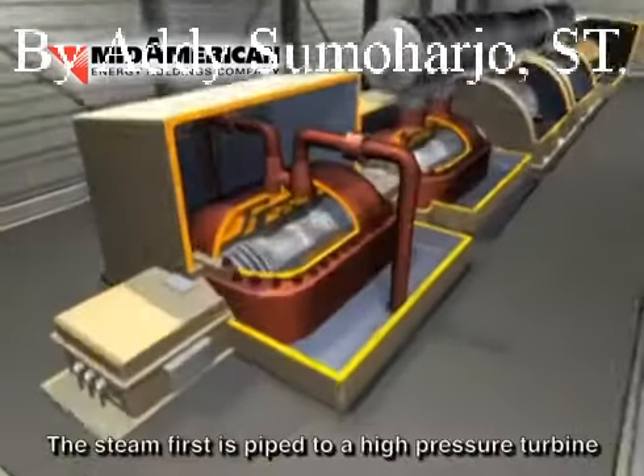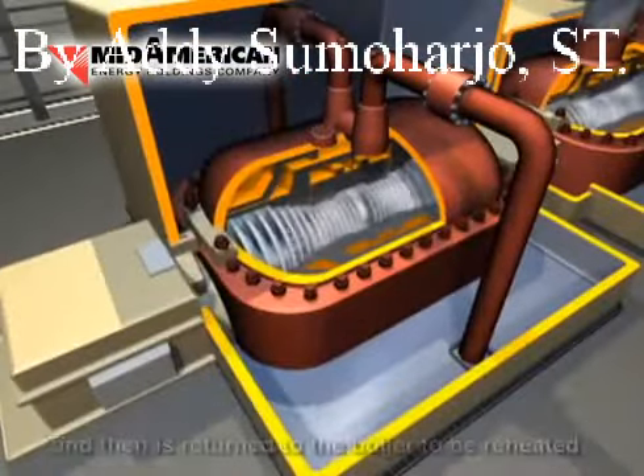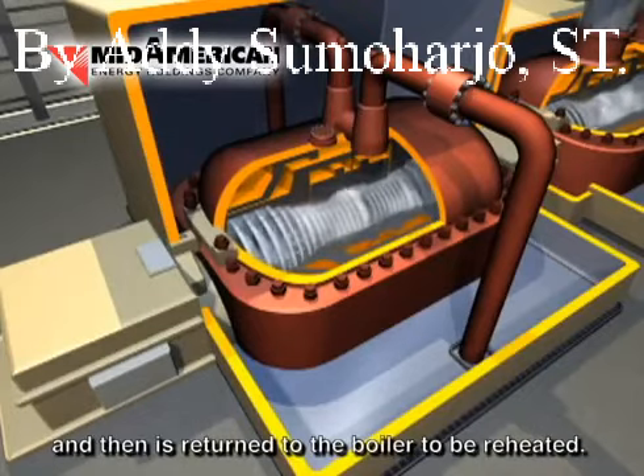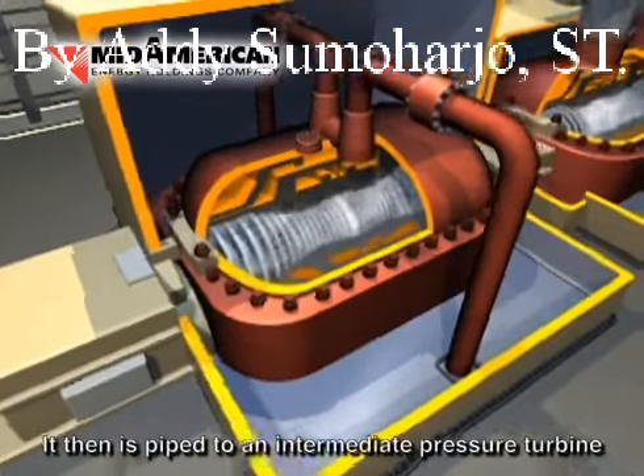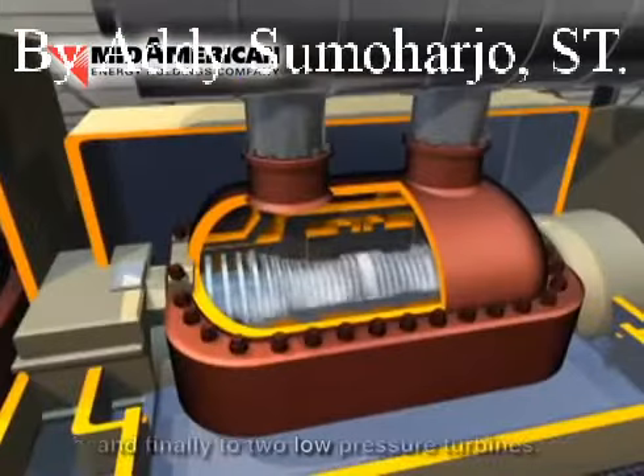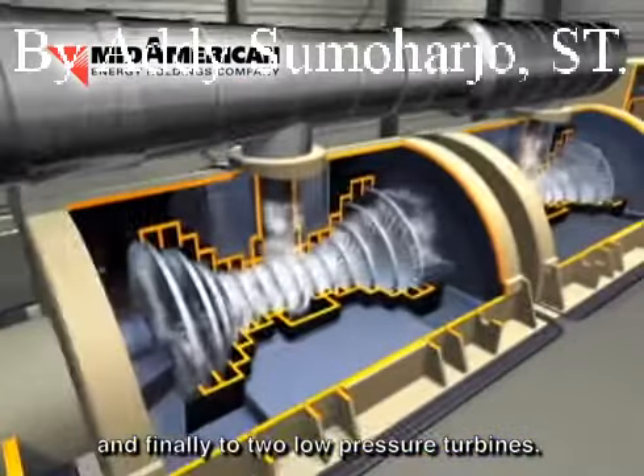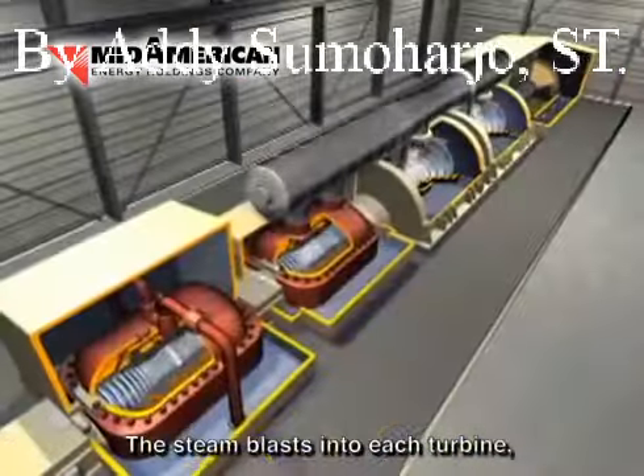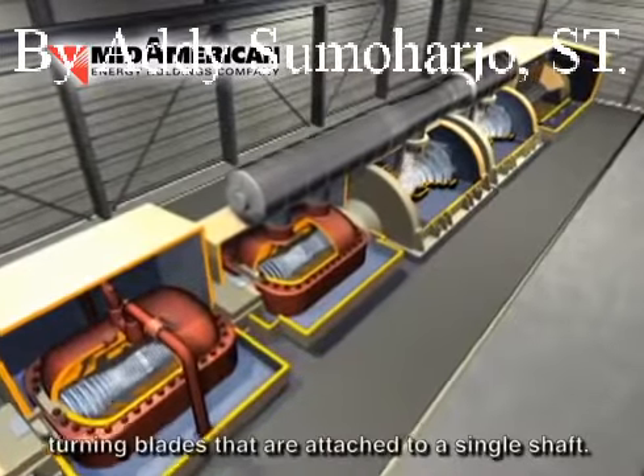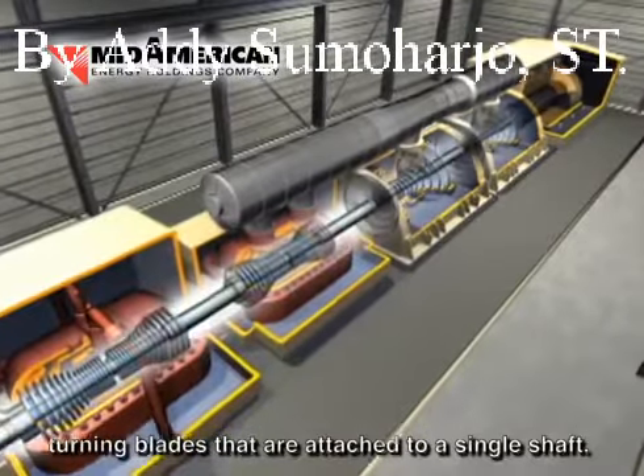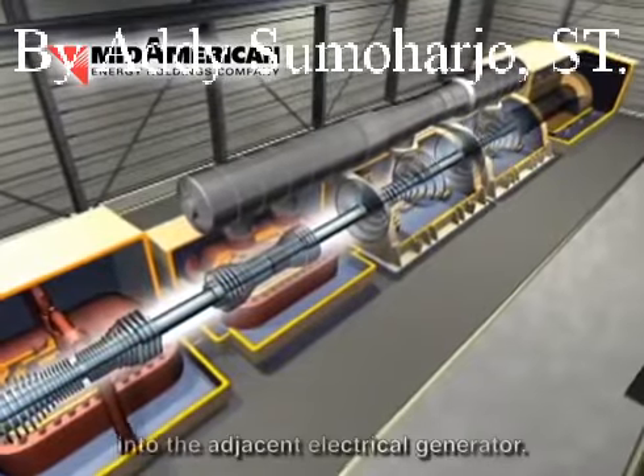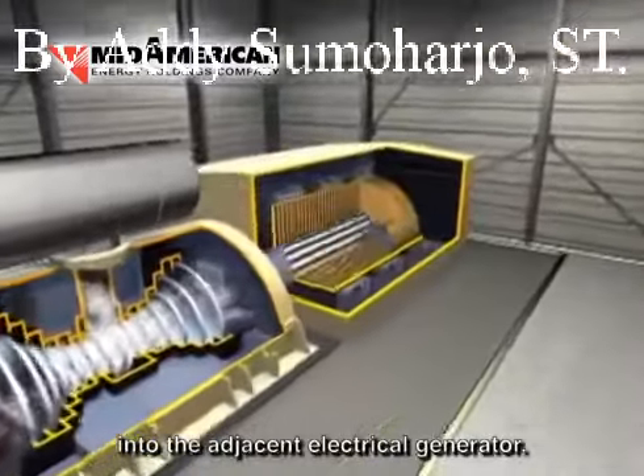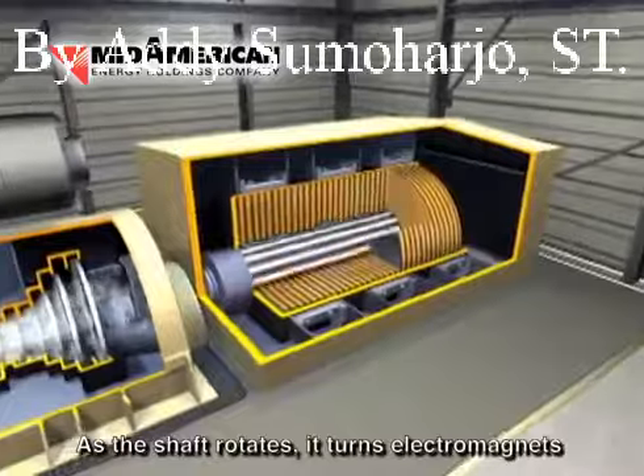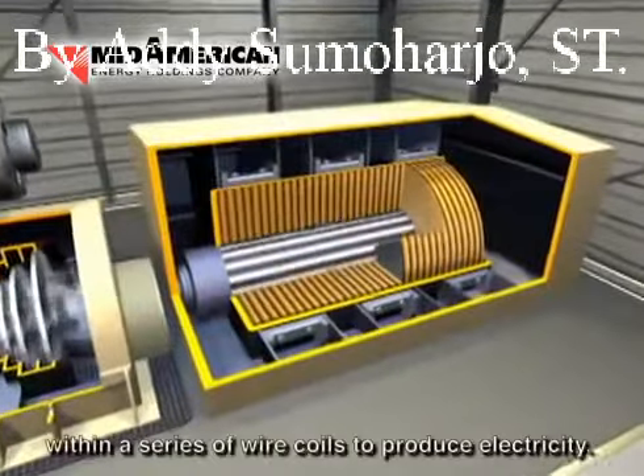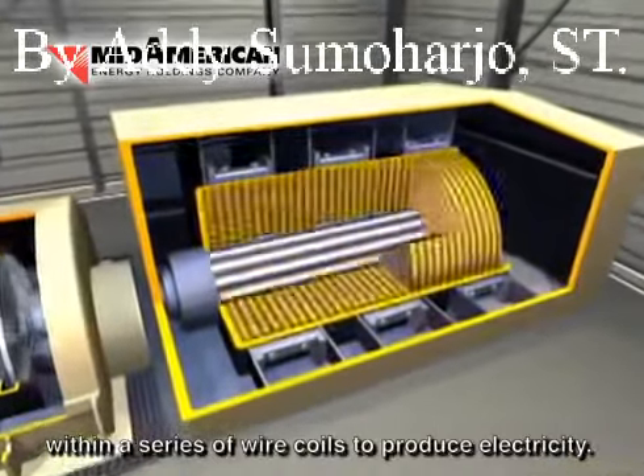The steam first is piped to a high-pressure turbine and then is returned to the boiler to be reheated. It then is piped to an intermediate pressure turbine and finally to 2 low-pressure turbines. The steam blasts into each turbine, turning blades that are attached to a single shaft. The turning shaft continues into the adjacent electrical generator. As the shaft rotates, it turns electromagnets within a series of wire coils to produce electricity.